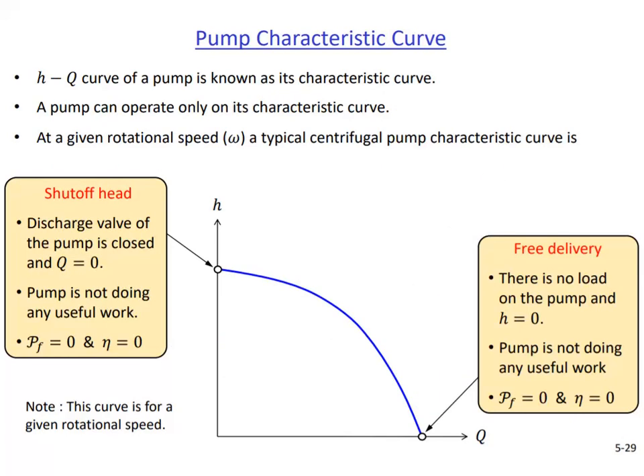A pump can operate anywhere on its HQ curve. It is the pumping system in which the pump is used that determines at which point exactly it operates. The two extremes of the HQ curve are known as the shutoff and the free delivery. Both of these are extreme conditions and should be avoided. The pump is not doing any useful work in these conditions.